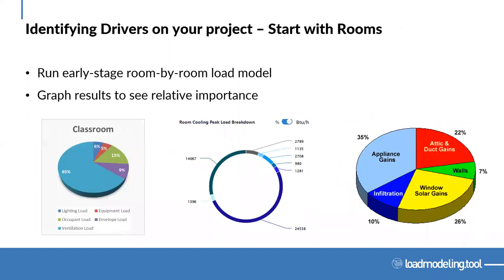Ways to identify that load — there are a couple of methods, but I think the first way is always to graph it. Go to your typical end uses — equipment, lighting, envelope, occupants — and just put them into a pie or donut chart, whichever fits your design best, and see what it looks like. You'll be able to very quickly see what's driving the load. Is it the solar gain? Is it the envelope load? The occupant load? This can be done quickly at early stage, room by room or for a whole building. Doing it room by room gives the advantage of drilling into the assumptions for those specific rooms, which will vary even at early stage.